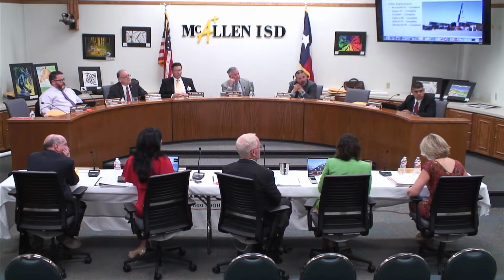We'll do the electrical in-house, and we'll have our on-call MEP engineer oversee the install. And then the manufacturer will be present for the startup to not void any warranties. So turnkey installed, between 50 and right now, 100? The industry right now calculates about $1,000 to $1,200 a ton for a turnkey job. We're achieving a little bit less than that by doing it in-house and saving, and being able to purchase the warranties.